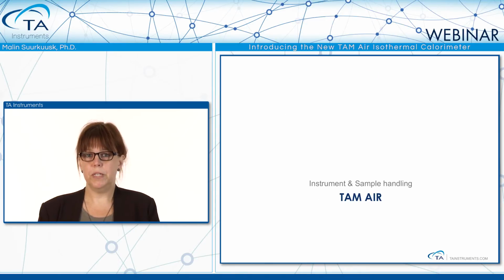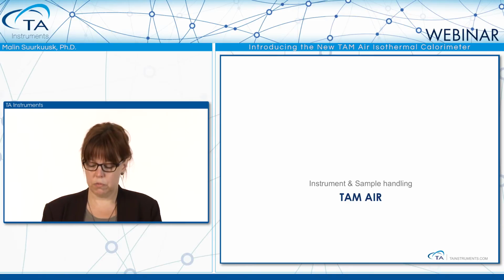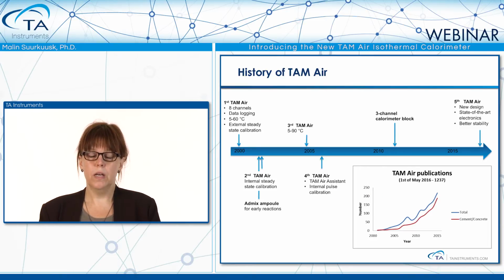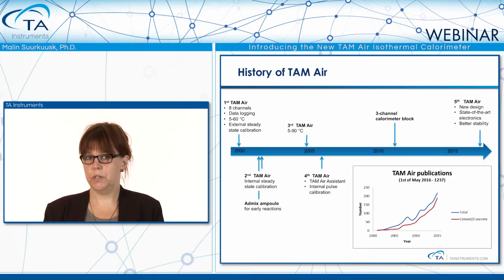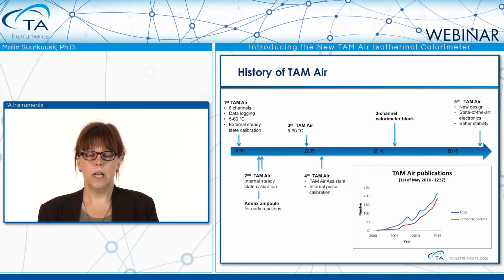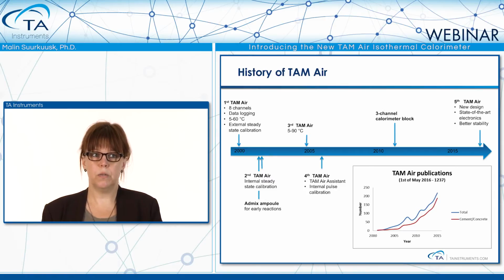So that was a very brief introduction to what calorimetry is, and now I would like to talk a little about the instrument itself, the TAM Air. First, if we start with the history, TAM Air was initially introduced in 2000, where the first TAM Air was actually specifically designed for the study of cement hydration. It was an 8-channel calorimeter, the same type we have today, with 20 milliliter sample sizes. It has a simple data logging software. The temperature range was up to 60 degrees, and there was an external calibration procedure.